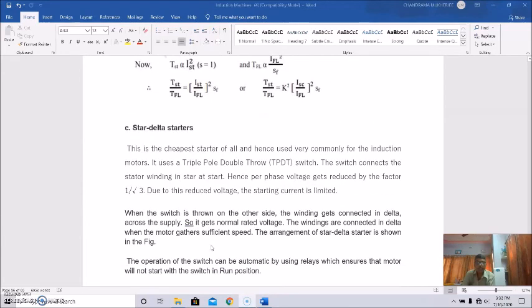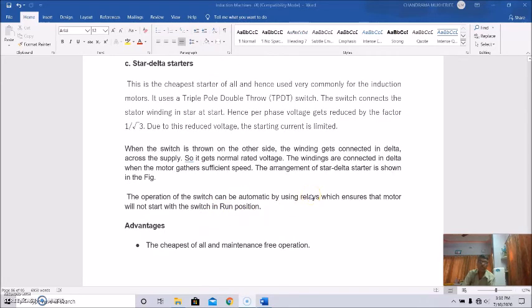So once again we can repeat this. This is the cheapest starter of all, and hence used very commonly for induction motors. It uses a triple pole double throw switch. The switch connects the stator winding in star at starting, and hence per phase voltage gets reduced by the factor 1 by root 3. Due to this reduced voltage, the starting current is limited. When the switch is thrown on the other side, the winding gets connected in delta across the supply. So it gets normal voltage, and the windings are connected in delta when the motor gathers sufficient speed.